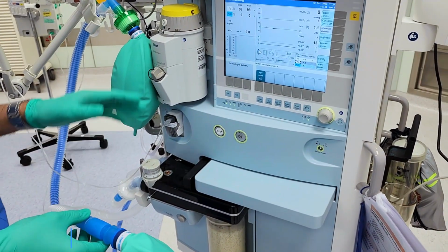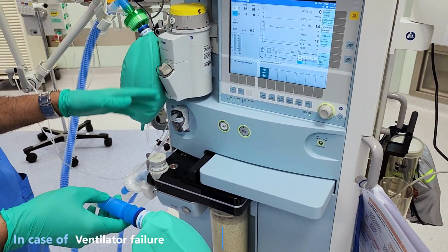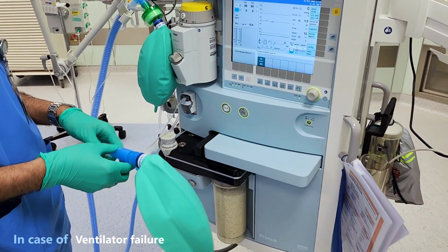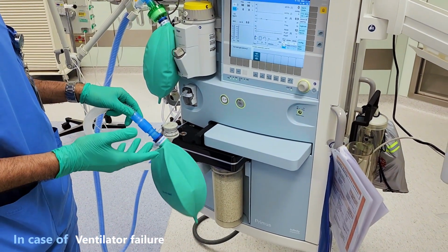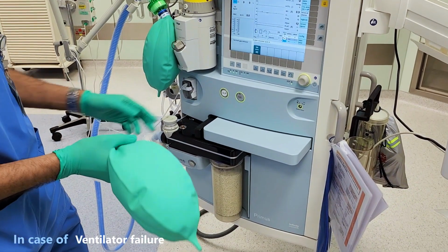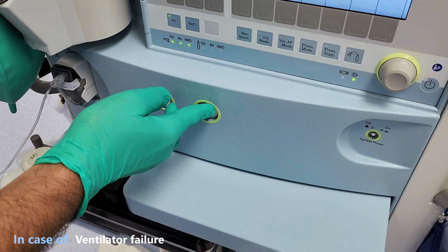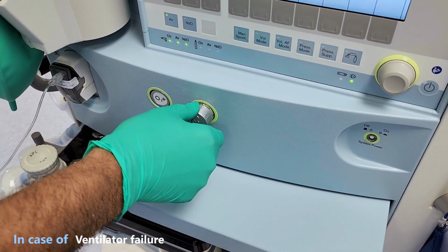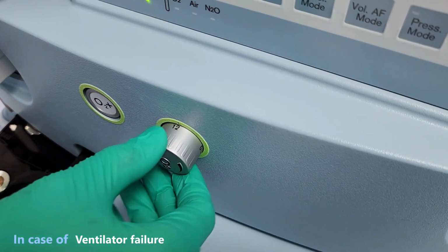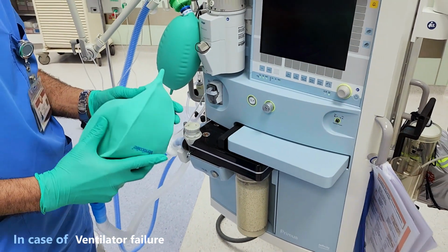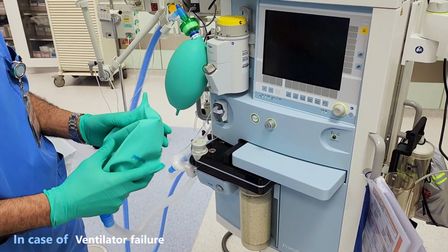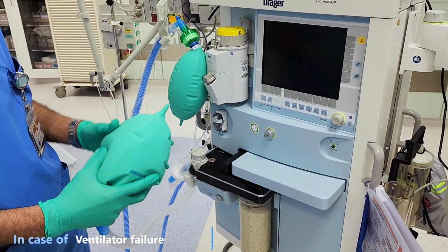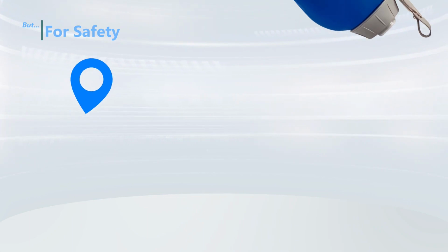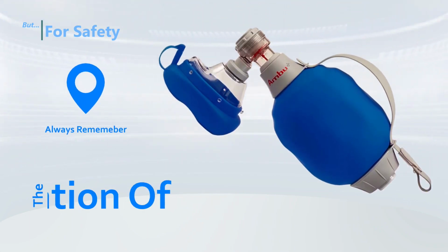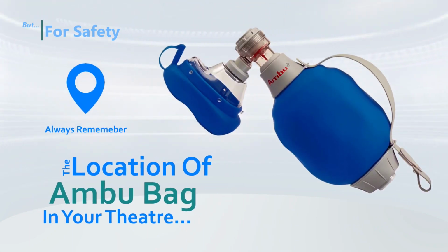Now what if the gas supply is okay, but the ventilator suddenly stops working, or there is a complete power supply failure, or we get an emergency patient and the machine was not switched on? We can still ventilate the patient by activating the emergency oxygen delivery system. Just push the button and adjust the flow. We will be able to ventilate the patient just as we do with the ambubag. And remember, this works even if the machine is still switched off, or even in case of complete machine failure. For safety, always keep the ambubag ready inside the theater and make sure you know its location.